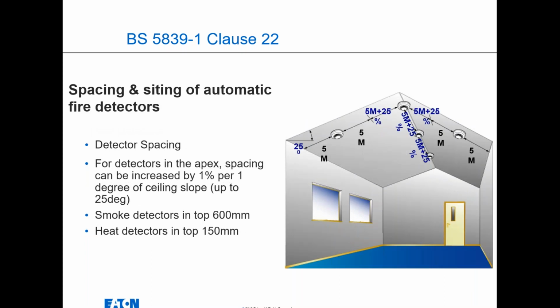So when you look at detector spacings, and detectors in the apex as well, they need to be at the highest point you can get to. Again, there is a calculation you can use to increase the detection spacing, because obviously when you've got an apex ceiling, smoke travels faster into that space, so you can increase the actual coverage. You can increase that by 1% per 1 degree of the ceiling slope, up to a maximum of 25 degrees.